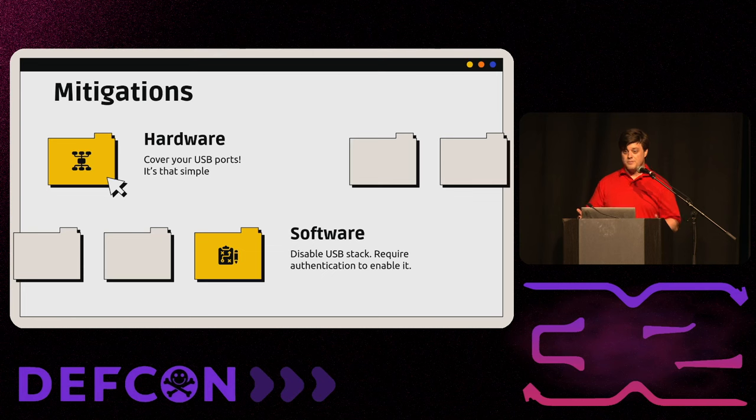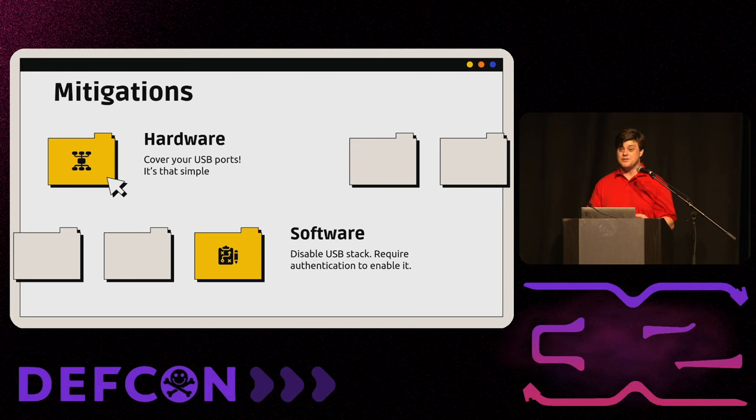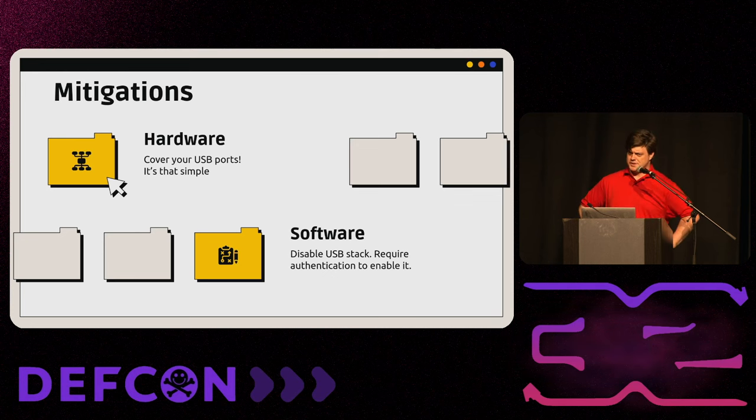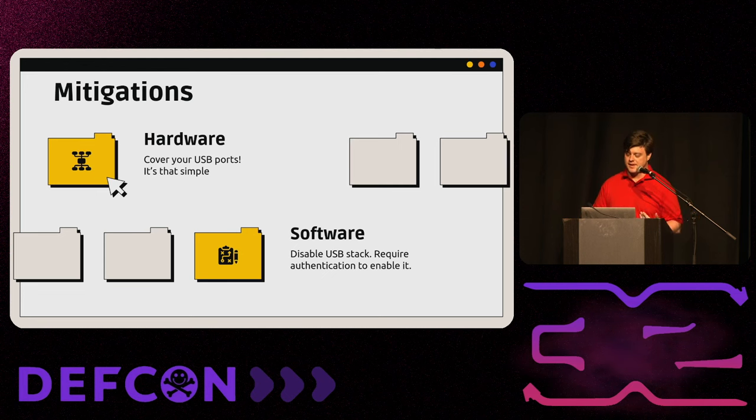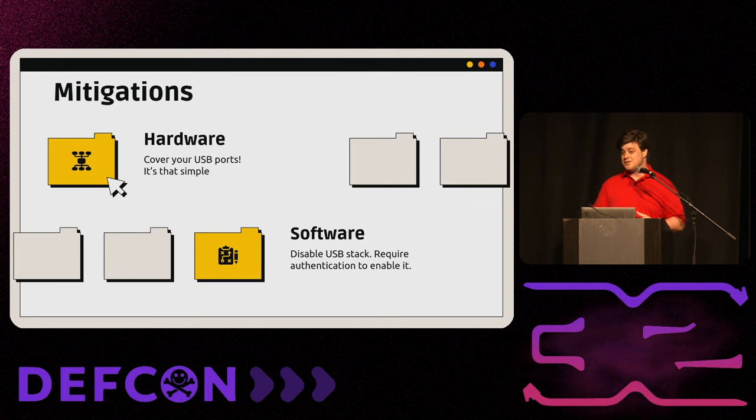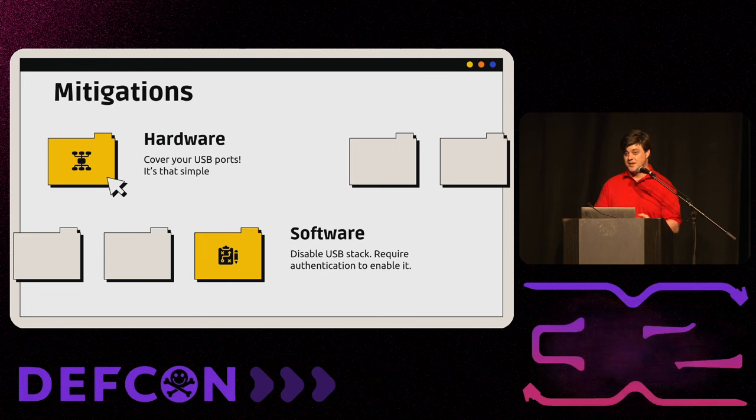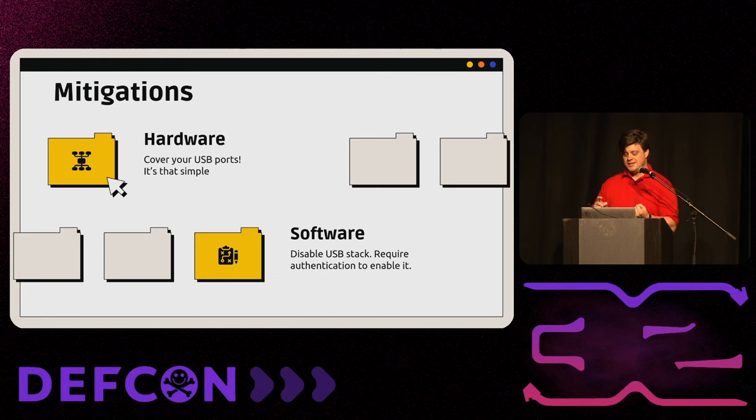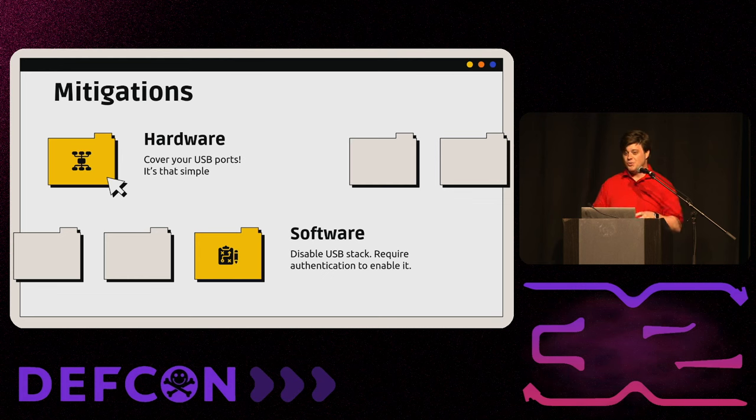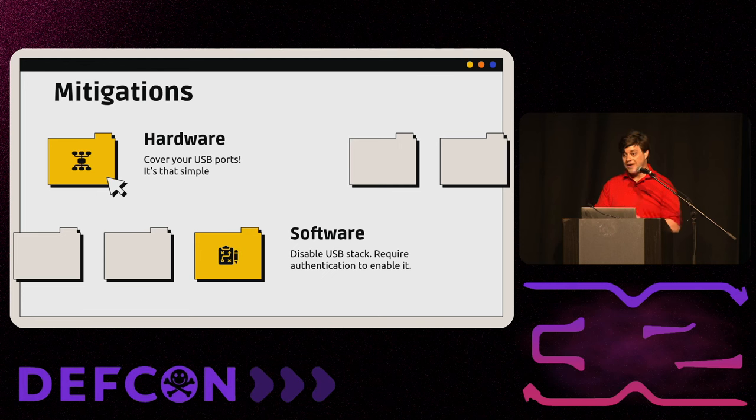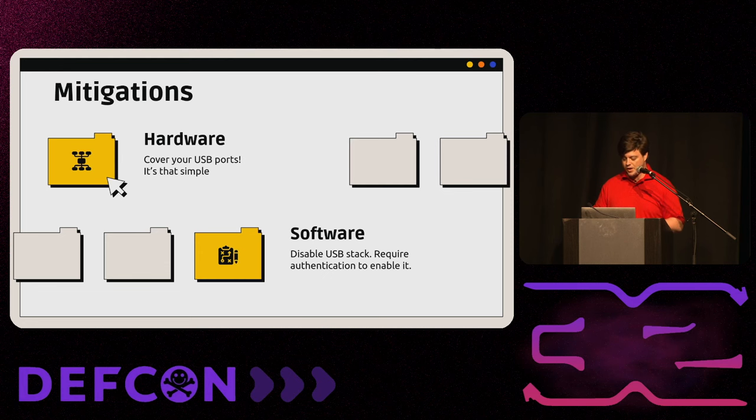Mitigations for anyone building a device. One, cover your USB ports. If you're not using them, cover them. If I need to take a Dremel to your device, then maybe you'd need extended physical access. Someone's going to notice that you were there. If you do need them for maybe service or something like that, then disable the USB stack until the user does something explicit, until they want to export a report, until they say, hey, I need to flash new firmware on the device, or I'm a service tech, and I've logged in with my special service tech password. Don't just have it open all the time. Only have it open when you need it, and that's a much smaller attack surface than just someone able to plug it in whenever they want.